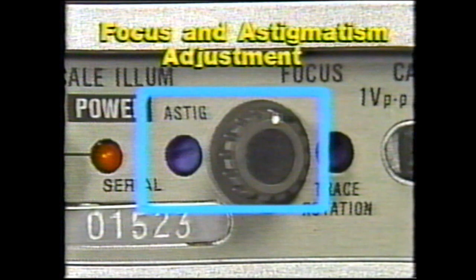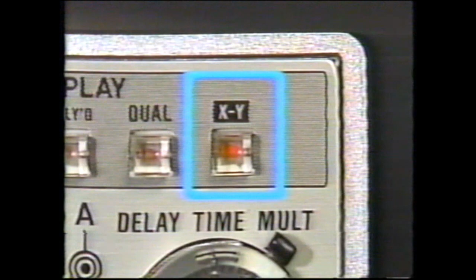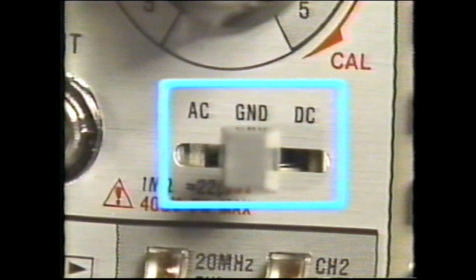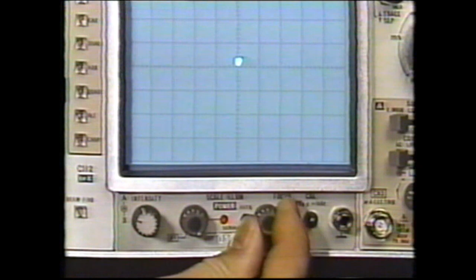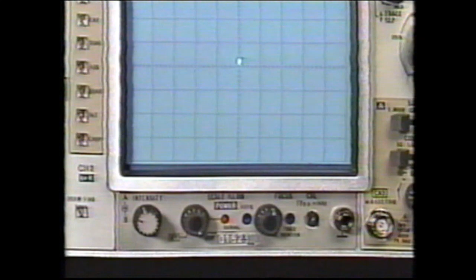The focus control adjusts the definition of a trace. The focus control works in conjunction with the astigmatism control, which determines the shape of the CRT beam. Ideally, it should be perfectly round. To adjust the shape and focus of the CRT beam, push the XY button and switch the AC ground DC switches to the ground position. This will provide a non-moving pinpoint trace on the CRT. Adjust the focus and astigmatism controls to form the smallest round dot possible on the CRT. This only needs to be checked and adjusted periodically.